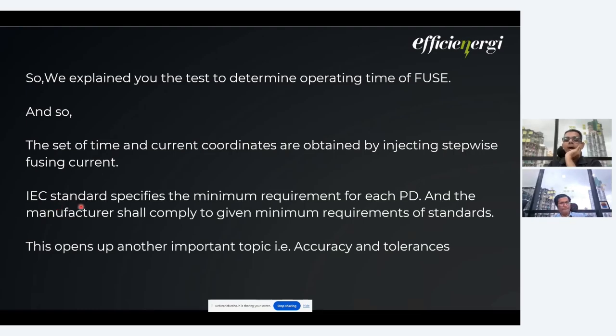I would like to add that there is a lot of literature available on the internet that gives information about these protective devices. But our attempt has been to bring out concepts which are not very easily available, and which, as I mentioned earlier, will allow you to build a base for properly understanding protective device coordination. While we do protective device coordination, all of these elements we have discussed so far, like operating time and time current characteristics, play a big role. Hence, it becomes very important for someone who is reviewing a protection device study to be able to appreciate the nitty-gritties that go into a proper PD study. So with that, we'll go to the next topic, accuracy and tolerances for fuses.